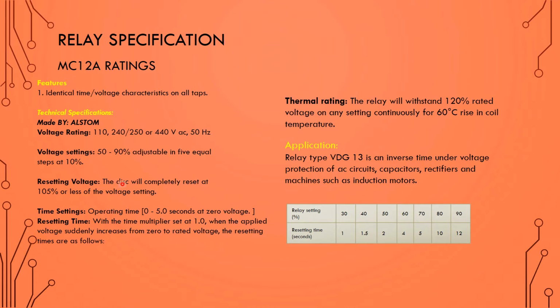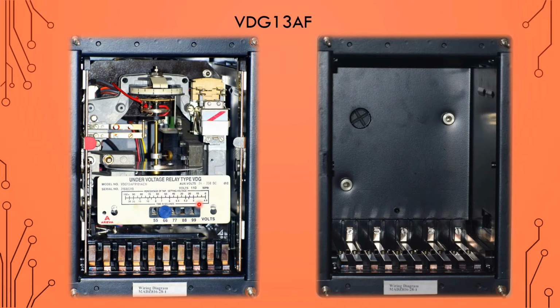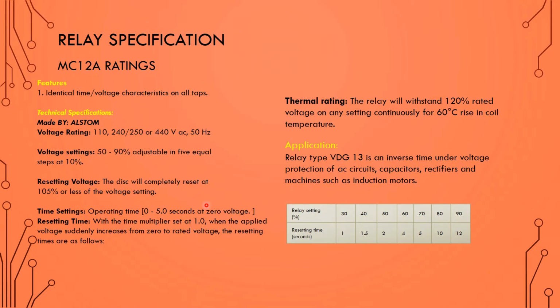The resetting voltage is such that the disk will completely reset at 105% or less of the voltage setting. For time setting, the operating time is 5 seconds at 0 voltage. That means when we give 0 voltage, as you can see here, it is 4.9 seconds, that means 5 seconds. In this way, we have to identify the characteristic or time setting.